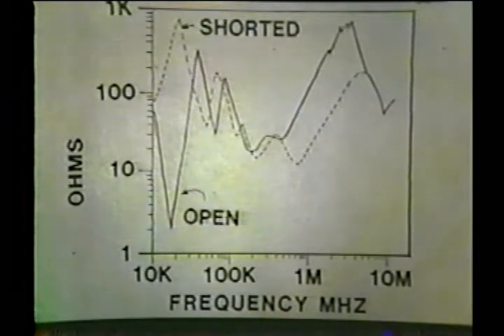In particular, at 19 kilohertz, the shorted line appeared to have a very high impedance of about 750 ohms. When the other end of that circuit was opened, it had a very low impedance. But this gives you somewhat of an idea that perhaps standing waves are occurring on the circuit in the machine.